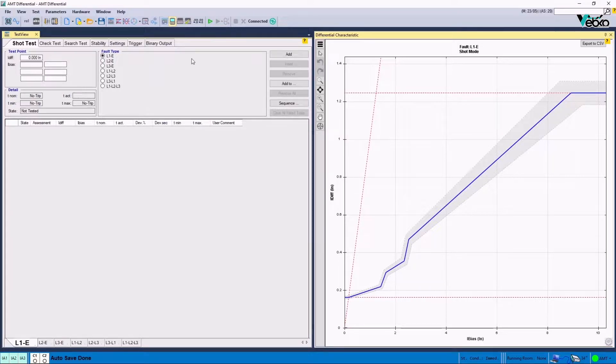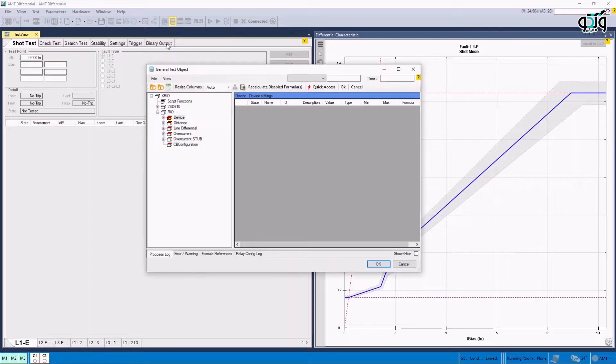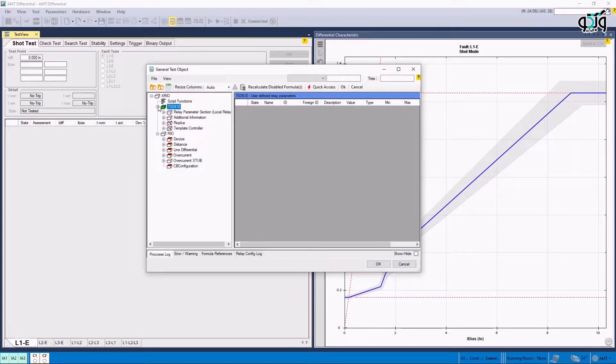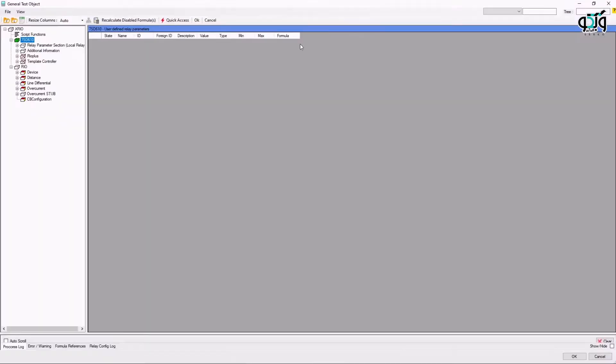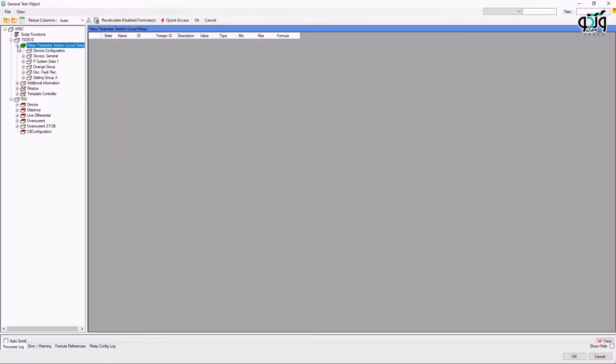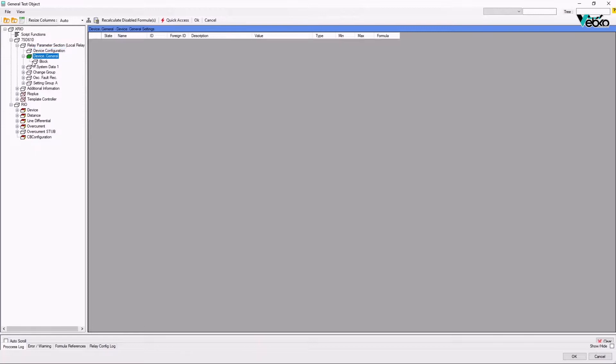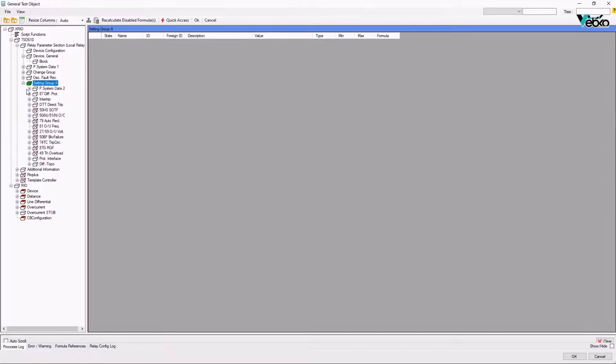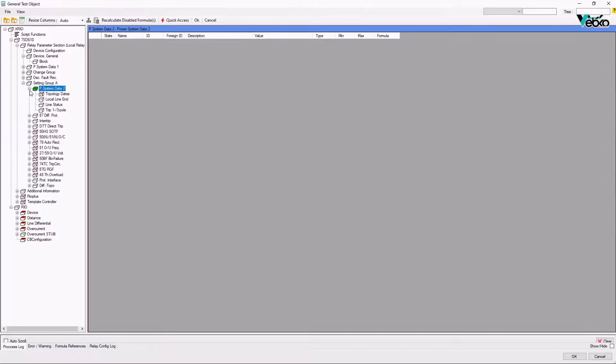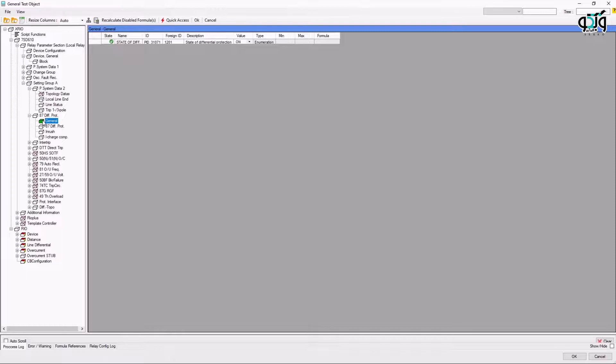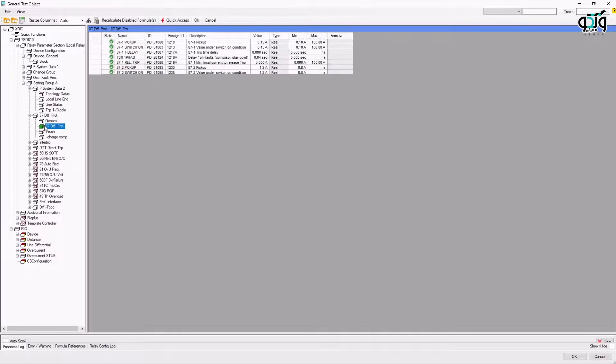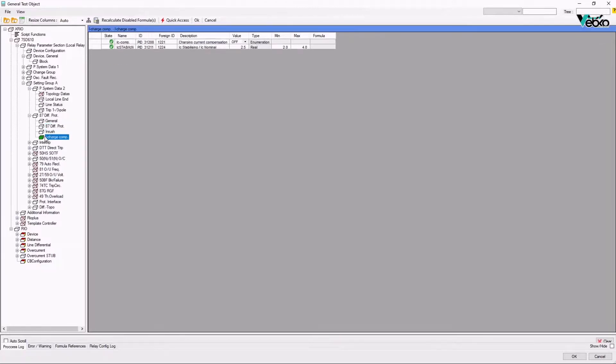Before beginning the test, the Test Object Parameters window is opened again, and 7SD610 subcategory is opened by clicking on the plus sign. In Relay Parameters section, it is possible to view the information related to the local relay or the current post in different subcategories. In Subcategory Setting Group A, it is possible to view the setting of different functions. By going to Subcategory 87 DIFF PROT, it is possible to examine the activity status of this parameter, time and current settings of pickup and trip, the inrush settings, and the parameter related to the charge of the line.